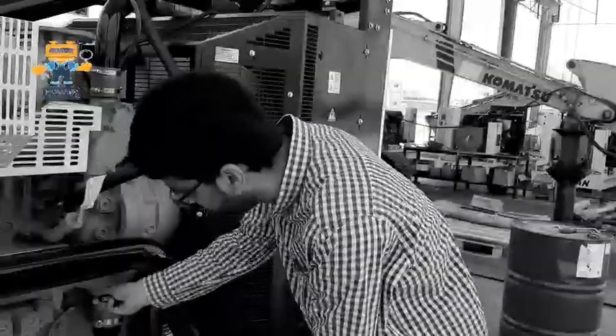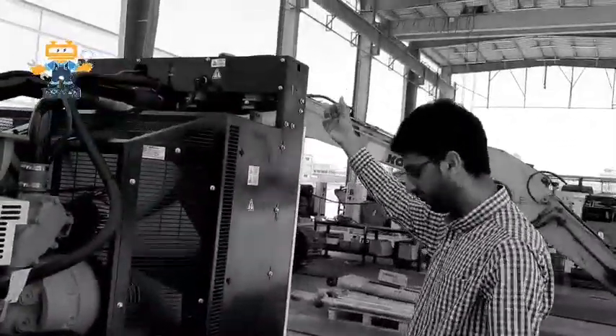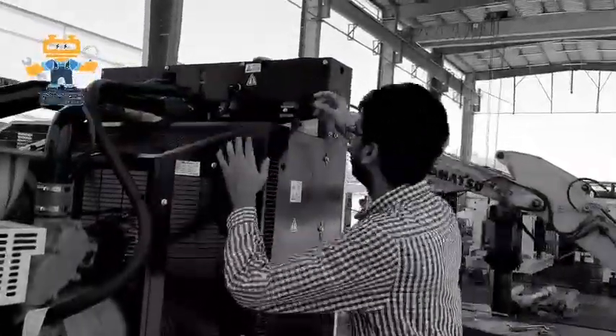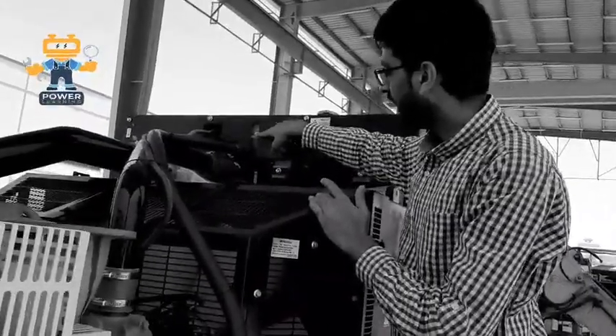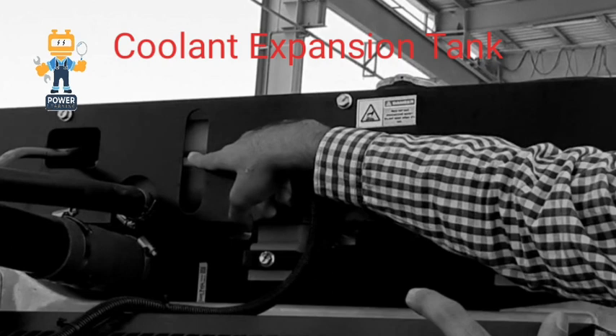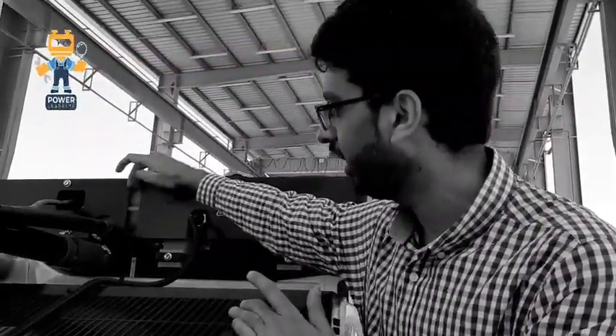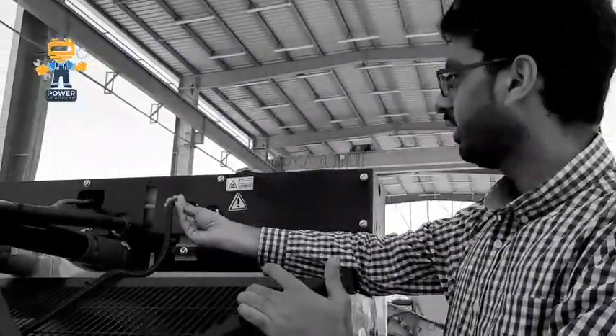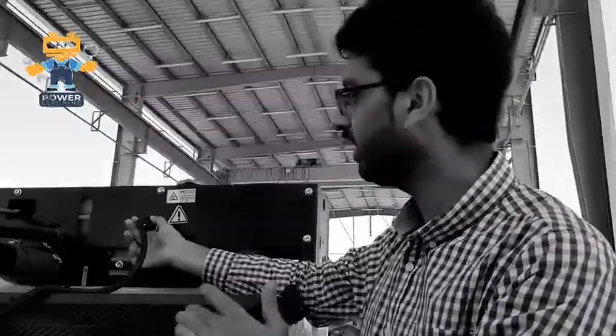So that is the first thing — we check the oil of the engine. After that, we have to check the engine coolant. As you see here, this is the radiator and this is the radiator cap. First of all, you have to check here in the expansion tank that it is full of coolant — the coolant is showing here, which means the coolant is available. And one more thing: this is called the water level switch. If the water level is lower than this switch, it will indicate us on the panel.